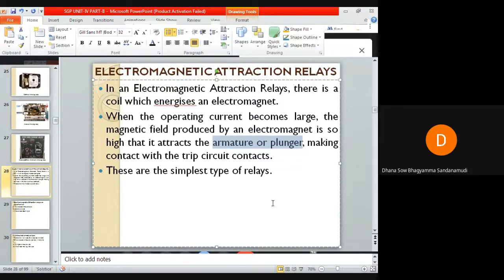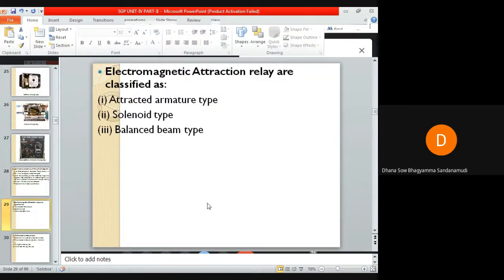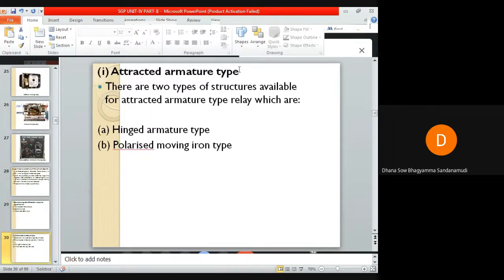In these relays, the relay coil energizes the electromagnet, and when a large operating current flows, the magnetic force attracts the armature or plunger towards the trip circuit contacts. Electromagnetic attraction type relays can be further classified as attracted armature type, solenoid type, and balanced beam type.